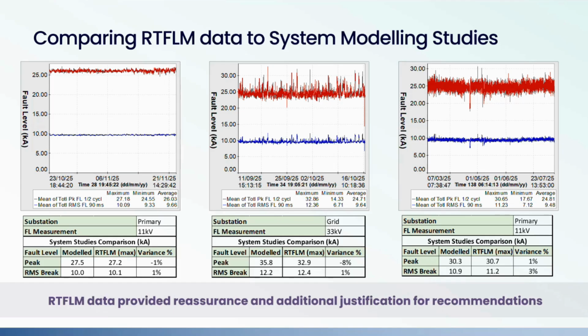On the right hand, I'll just go to the right hand one first, which is another primary substation. This is an older substation with a lot more connected to it. Again, we're measuring fault level at 11 kV, and there are measurements over a period of several months. The maximum that the fault level monitor measured during that period was 30.7 kA, which is 1% higher than the 30.3 kA that the models were telling us to expect. And again, with the RMS break, slightly higher, 3% over that period. But when you look at the traces, you can see that those peaks are very infrequent, and the vast majority of the time the fault level is lower than that.